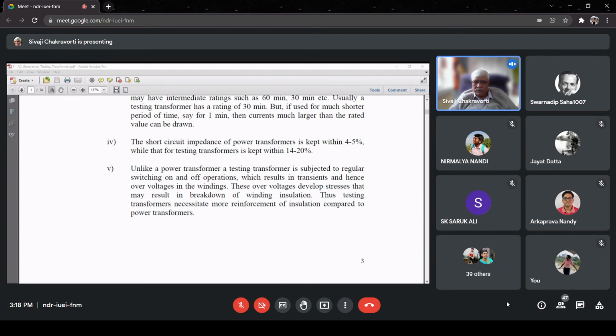They measure the ohmic value. Then the numerator is rated current multiplied by that ohmic value. It becomes a voltage drop. And the denominator is the rated voltage. So this percentage is nothing but the voltage drop as a percentage of the rated voltage. So 4% impedance means that the series impedance will cause a voltage drop at rated current of 4% of the rated voltage. That is how we represent it. After that, you can do all sorts of per unit and all that. But fundamentally, it is the voltage drop in the series leakage impedance as a percentage of the rated voltage.